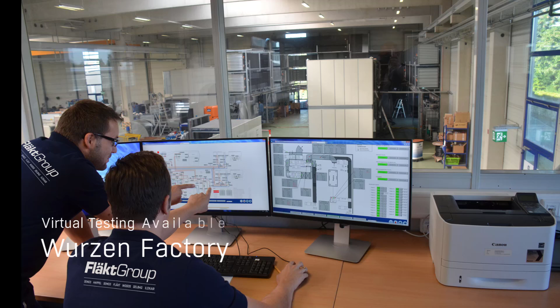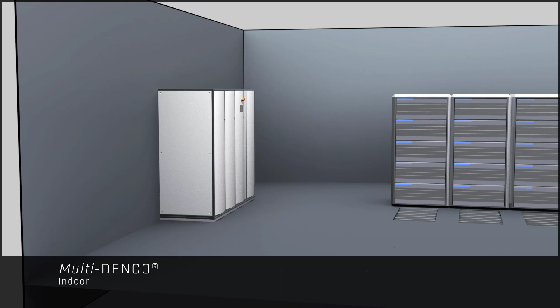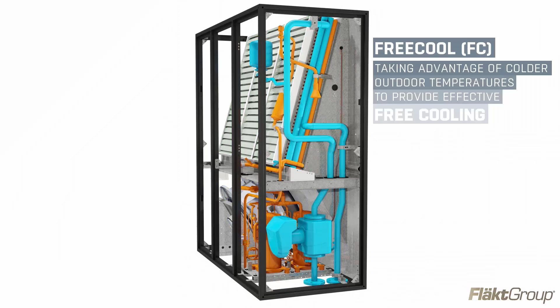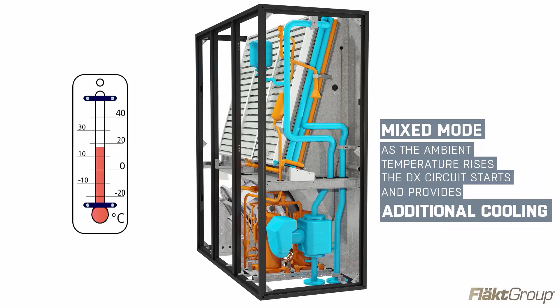The most common product that's deployed into those facilities is the Multi-DENCO product. This product has heat rejection via direct expansion, chilled water, or a free cooling product where we use an indirect free cooling circuit, a glycol circuit, to take advantage of the cold winter temperatures within the UK, driving down that glycol water temperature, enabling us to switch off the direct expansion system, which is the most expensive system to run within a Multi-DENCO unit, and utilize that free cooling that we have available.